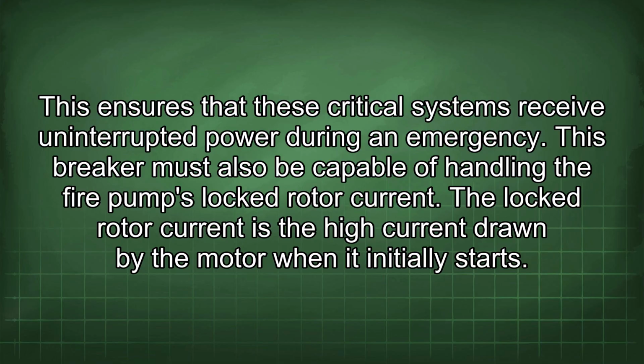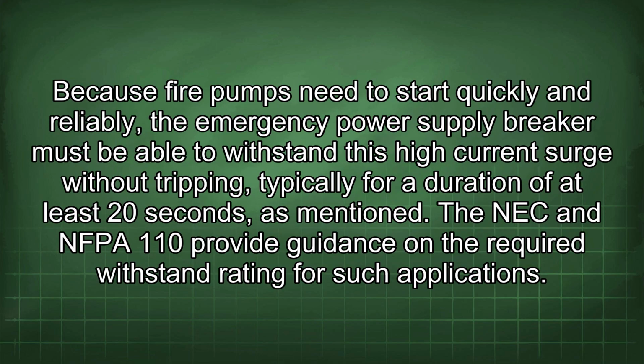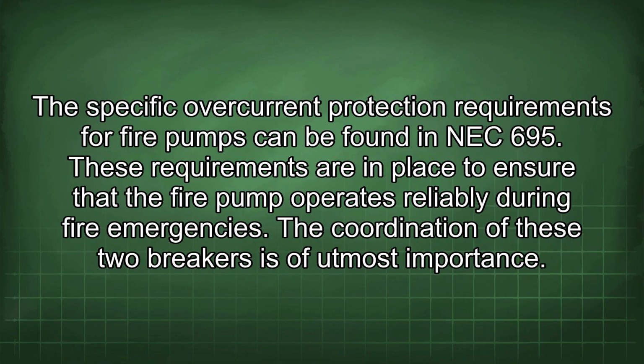The locked rotor current is the high current drawn by the motor when it initially starts. Because fire pumps need to start quickly and reliably, the emergency power supply breaker must be able to withstand this high current surge without tripping, typically for a duration of at least 20 seconds, as mentioned. The NEC and NFPA 110 provide guidance on the required withstand rating for such applications. The specific overcurrent protection requirements for fire pumps can be found in NEC 695. These requirements are in place to ensure that the fire pump operates reliably during fire emergencies.